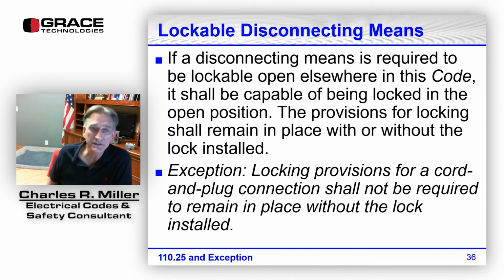Lockable disconnecting means: if a disconnecting means is required to be locked open elsewhere in the code, it has to be capable of being locked in the open position. The provisions for locking have to remain in place with or without the lock installed. This is 110.25. This hasn't been in Article 110 all that long. Before it was in 110, every section that referenced that the disconnecting means had to be lockable.